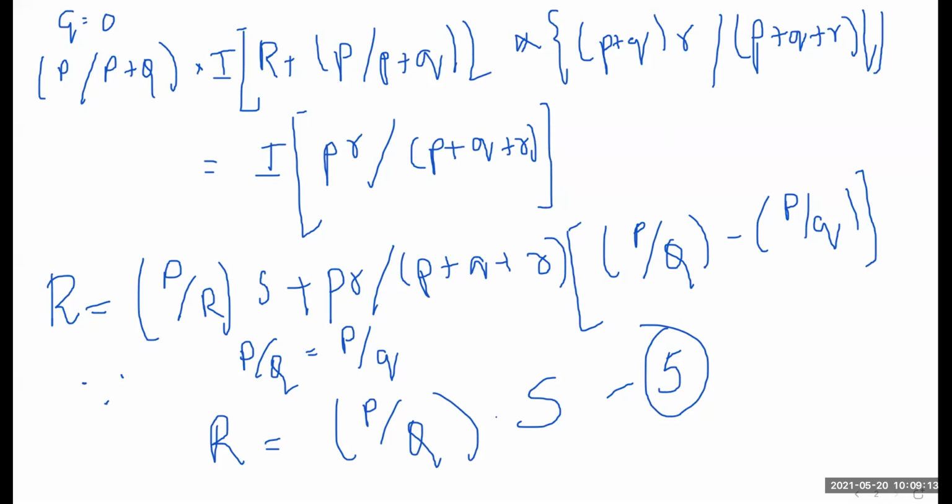Typically, I told you it measures 1 to 0.00001 ohm, and it gives an accuracy of plus minus 0.05% to plus minus 0.2%.